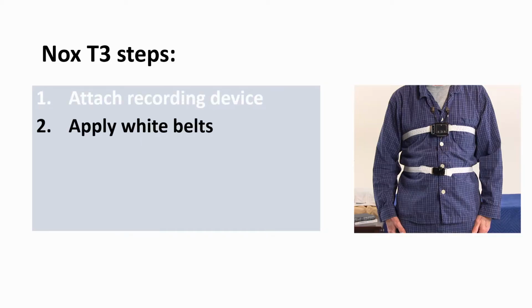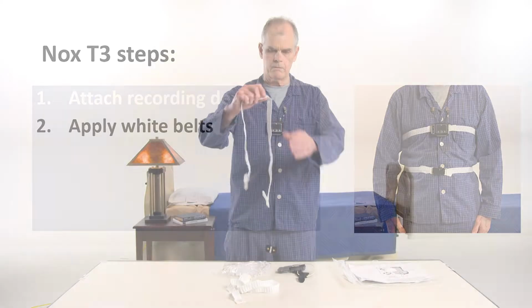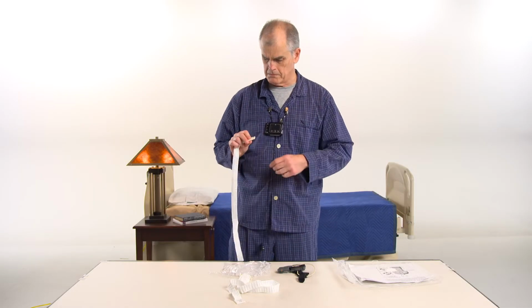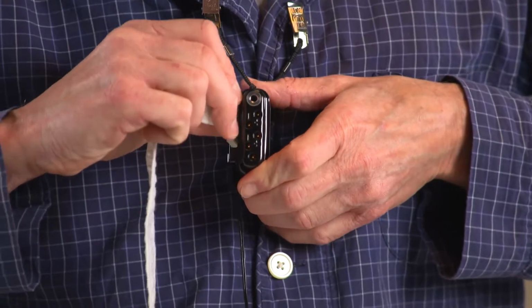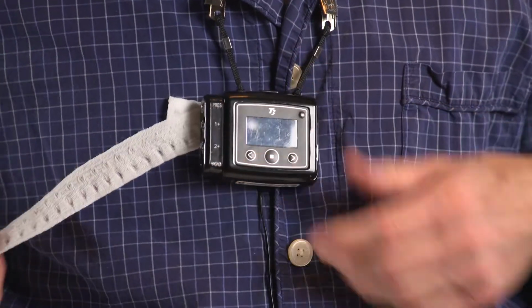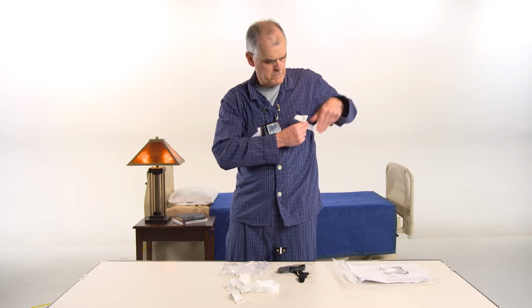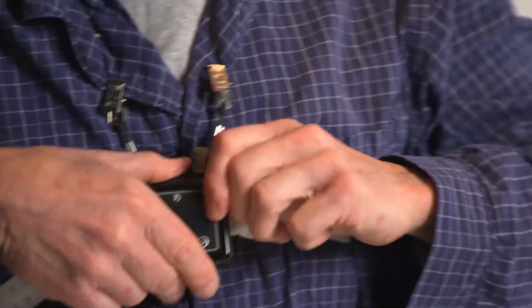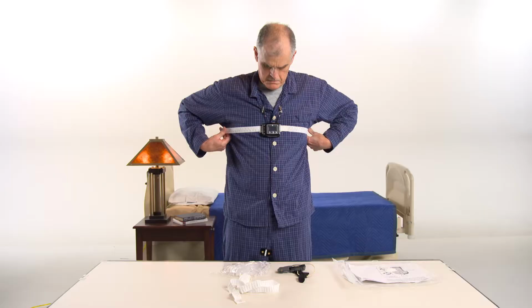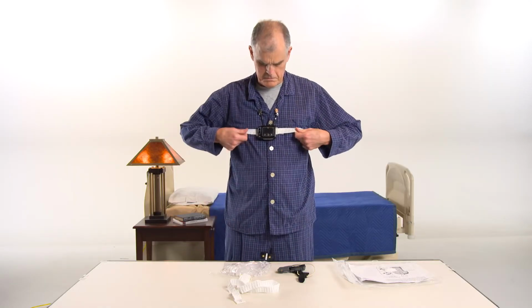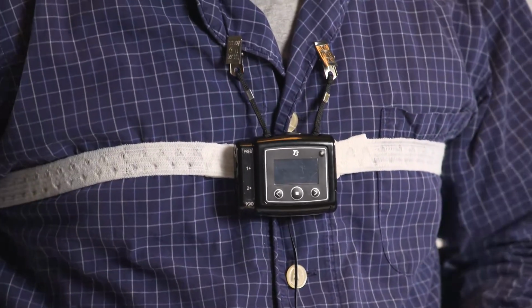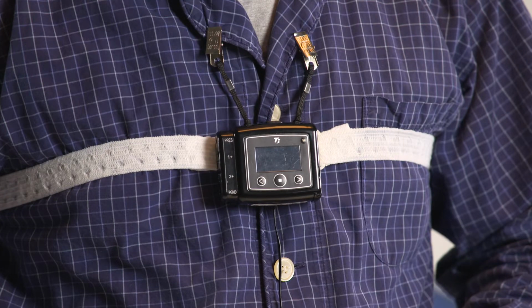The next step is to apply the white stretchy belts around your chest and abdomen. One or both belts may already be partially assembled. Take one belt and snap it to one side of the Nox T3 recording device. Wrap the belt around your upper body and snap the other end in place on the back of the device. Once in place, position the belt so that it is about 1 inch below your armpit. The belt needs to be snug, but not too tight. To tighten the belt, pull the loop until the belt is secure yet comfortable. Please be aware that the belts are adjustable in only one direction. They can only be tightened, not loosened, so adjust slowly.